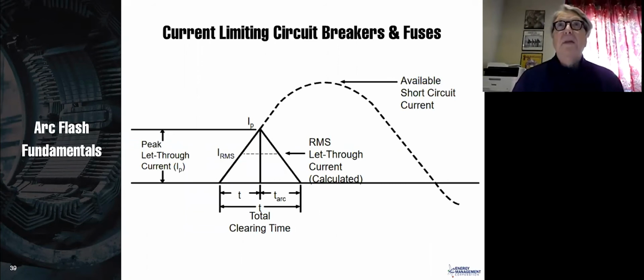Now, I was an engineer with Westinghouse when they came out with the very first high interrupting circuit breakers. And you know that they have all kinds of ratings on circuit breakers that are 5 kA, 10 kA, 15, 25, whatever. But then the higher interrupting breakers are always 65 and 100. Westinghouse came up with that because if you have a 2500 kVA transformer and a reasonable amount of motor contribution, then the fault current from that transformer is going to be 65 kA or less. And that's where the 65 kA breaker came from, to allow engineers to specify 2500 kVA 480 volt transformers. Prior to that time, and this was in the 80s, engineers tried to have their largest 480 volt distribution transformers be 1,000 kVA or less, and these days 2,500 kVA is common, and that's because of these breakers.